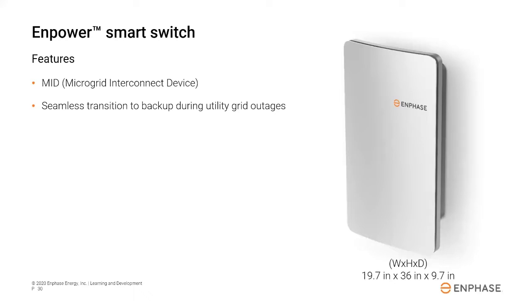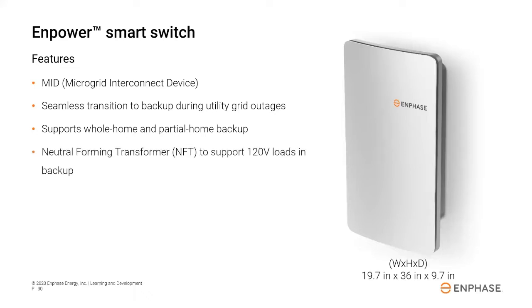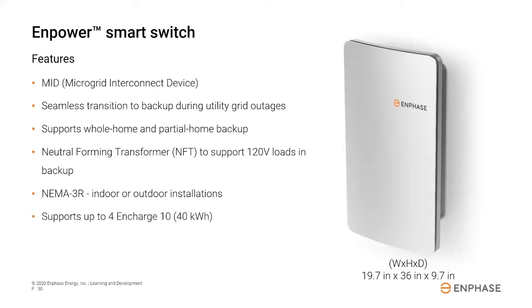Then, once the utility grid is back up, it detects the frequency and syncs to it for a very smooth transition back to being grid connected without flickering lights. The Enpower can be used as either a whole home backup or a partial home backup disconnect. It has a built-in neutral forming transformer, which is required in order for the system to support both 240 volt and 120 volt loads. And just like the Encharge batteries, the enclosure rating is NEMA 3R, so it can be installed inside or outside. Up to 4 of the Encharge 10 units, or any combination of 3s and 10s that equals that, can be connected to a single Enpower for a total of 40 kilowatt hours of energy storage, which is about 15 kilowatts of continuous power.